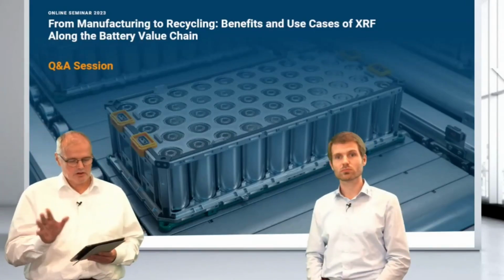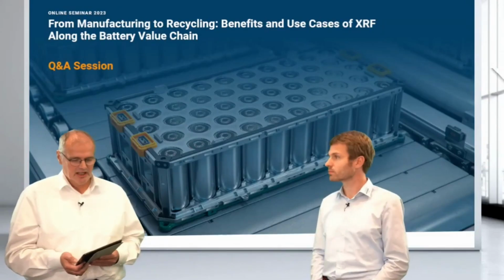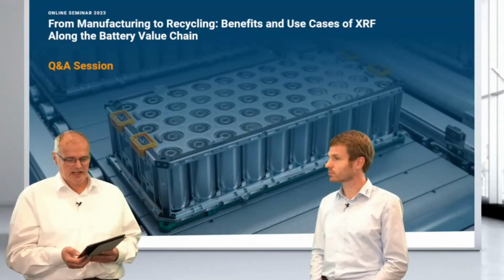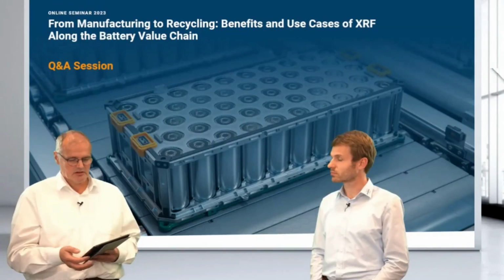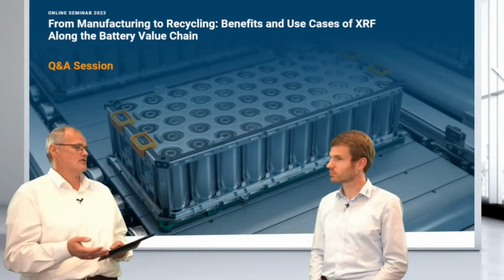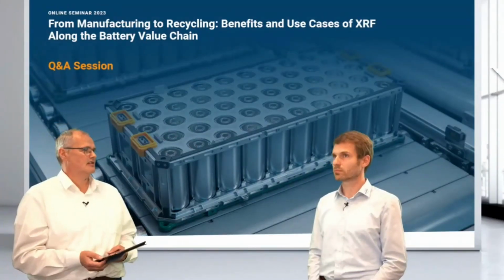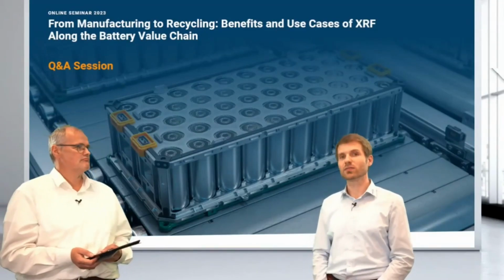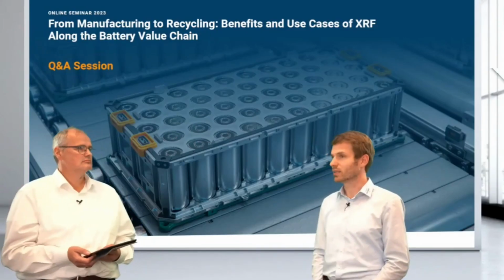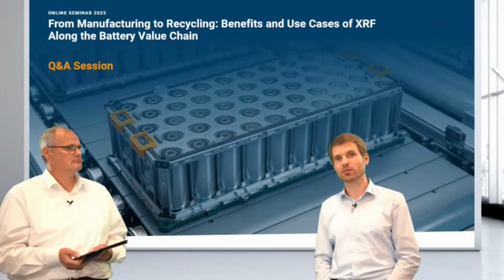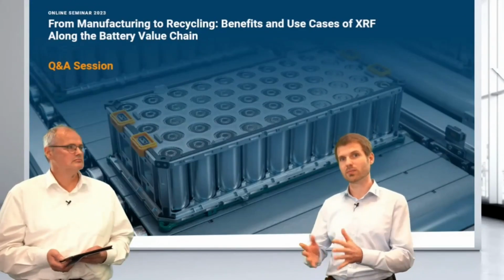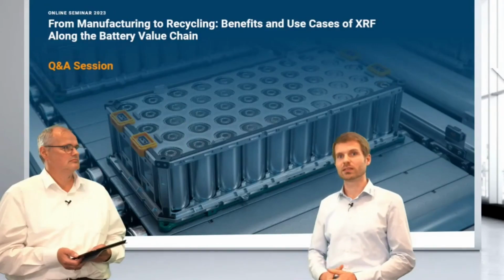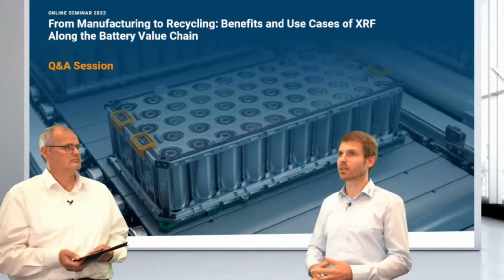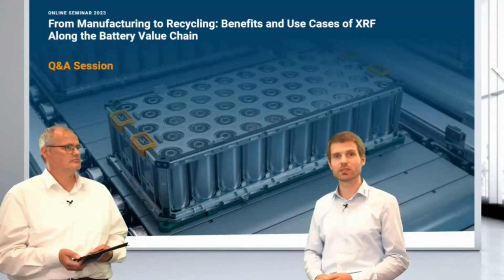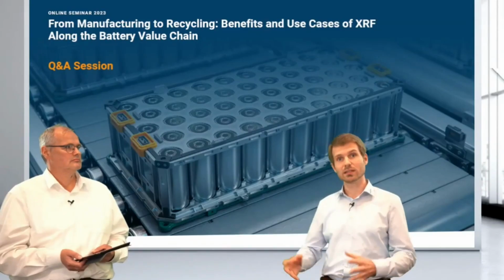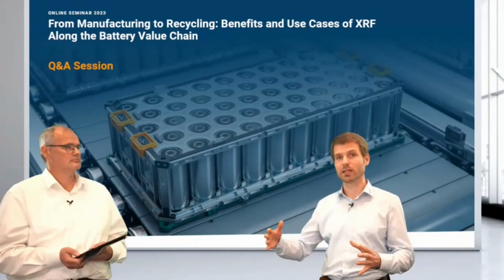That's a rough estimation. One of the last questions we are answering today concerns measurement accuracy: which deviations can be seen concerning the grain size particle effect? The grain size has an effect. Normally there is a sweet spot for XRF, where you get the best signal and data, on the order of a few tens of microns, so 40, 50, 60 microns. That's ideal. But you can also get very robust results for much larger particles.